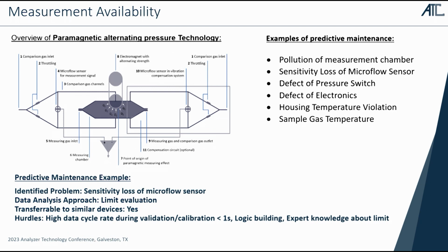I brought 4 of them for 4 different technologies with me. But of course, the same approach you can apply for every analyzer. If it's a TOC analyzer, pH sensor, conductivity, it's possible for every device. You have to look into the individual device from each vendor to see what is possible. But now let's talk about an oxygen measurement we have. So paramagnetic alternating pressure technology here.